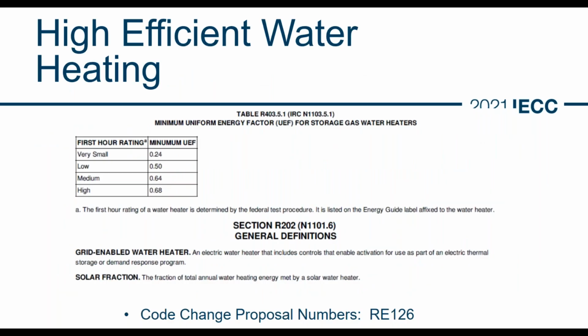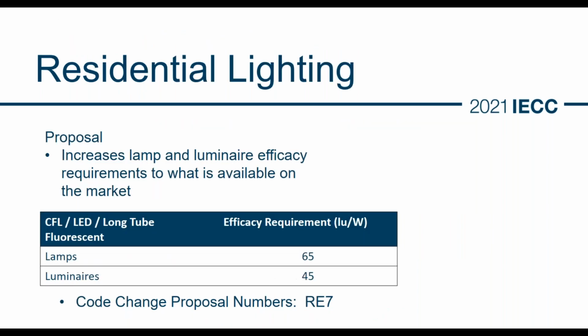This particular one, we mentioned the uniform energy factor on here, and here's the table for that. So this is a new rating system for residential scale water heaters, and the requirements we just showed above would apply to this particular table. Based on your first hour rating, from very small up to high, these are the UEF values you have to have. Slightly more efficient than the base case water heaters, but it does reduce your water heating load for that building. So if we can go to the next slide, please.